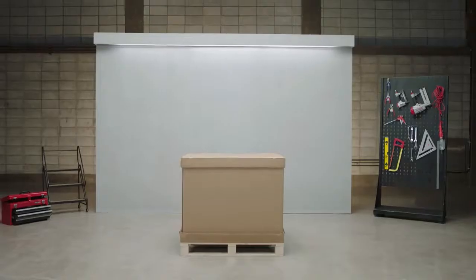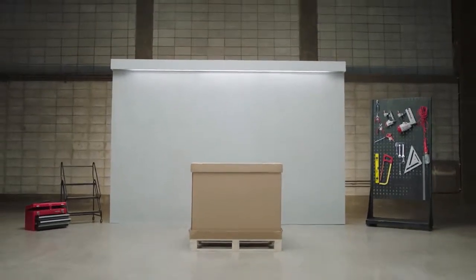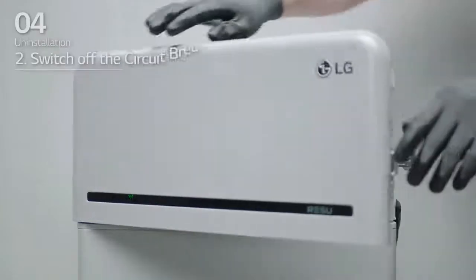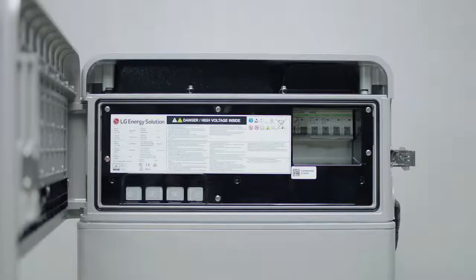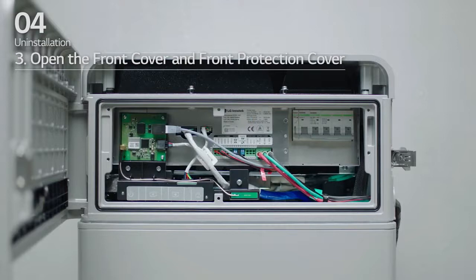Uninstallation. LG Energy Solution will show you how to uninstall the RESU16H Prime. Prepare tools for uninstallation. One: switch the inverter off. Two: open the front cover and switch the circuit breaker off — make sure it is in the off position. Three: loosen the six bolts and remove the front protection cover.